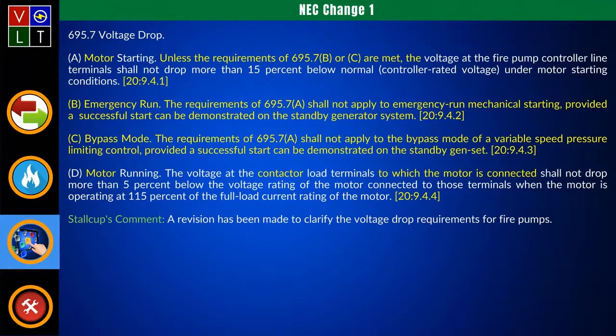Because when you look at that, it'll tell you, unless the requirements of 695 B and C are met, the voltage at the fire pump controller line terminal shall not drop more than 15% below the normal controller rated voltage under motor starting conditions. And didn't we already do voltage drop as a myth?